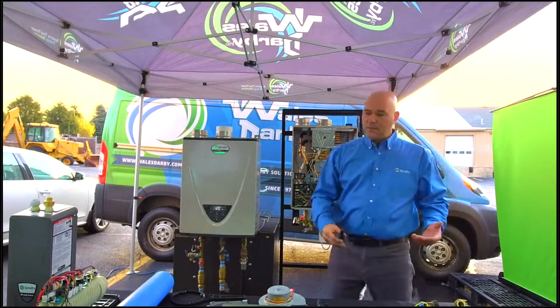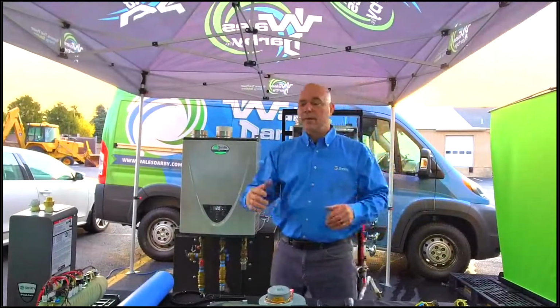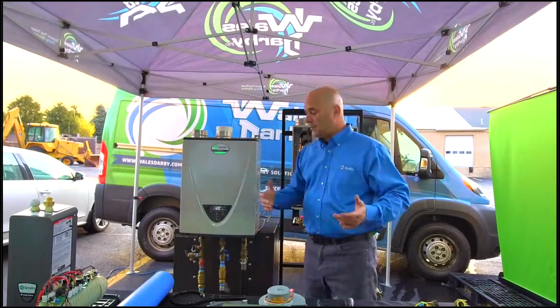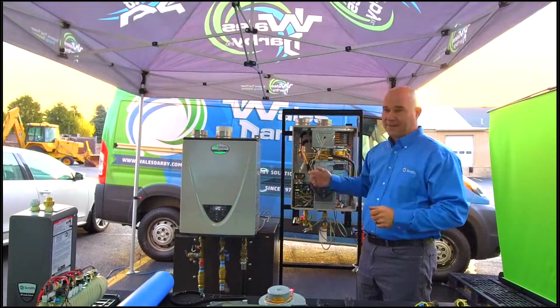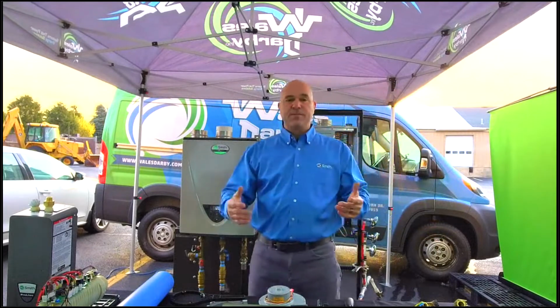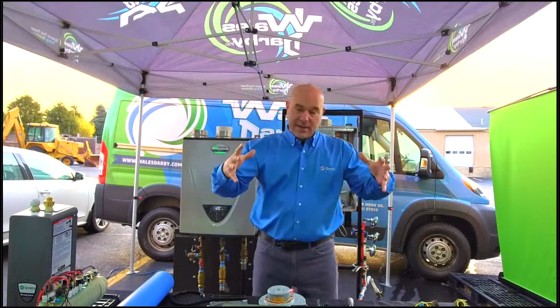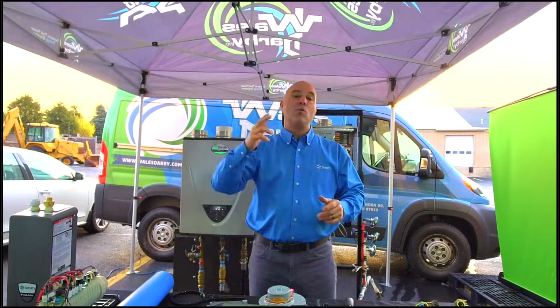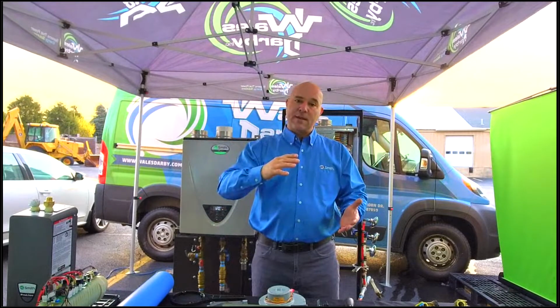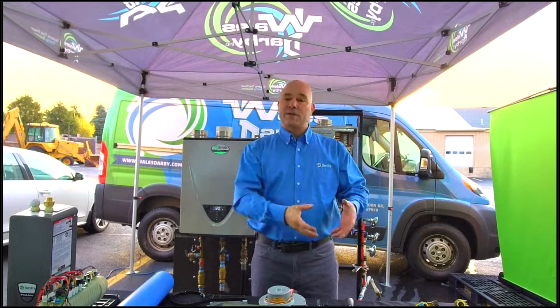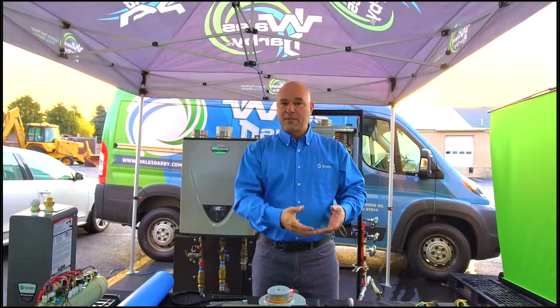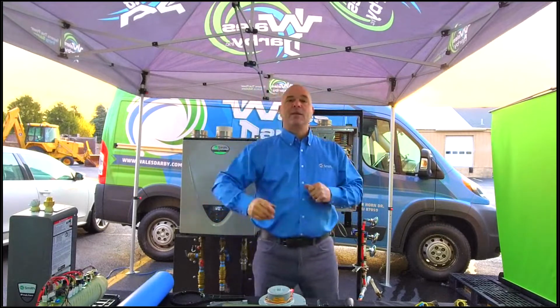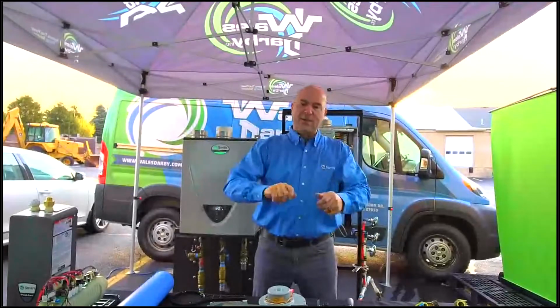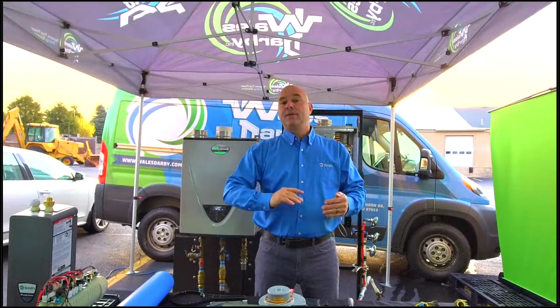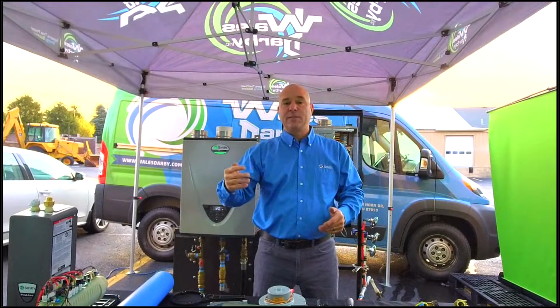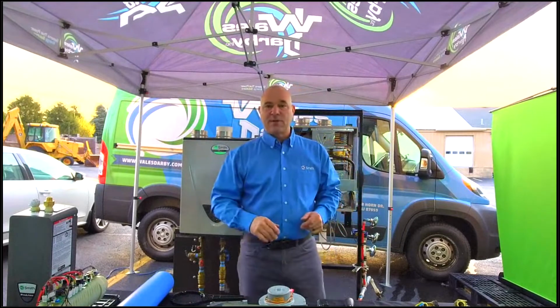I always start this with, what's the difference between a tank style water heater and a tankless water heater, right? Because that's really the fundamental difference that we need to understand before we go to a tankless type product. So I got up early this morning and hopped in the shower. Let's say I have a tank style water heater. I got in the shower. I started to draw water off of the water heater, and the water heater started to take on cold water from the home. When that took place, it told the control there was a water draw by dropping the temperature at the control. It fired the unit, and the unit ran probably the whole time I was in the shower. I got done, I shut the faucet off, and the tank style water heater probably continued to operate until it made temperature.